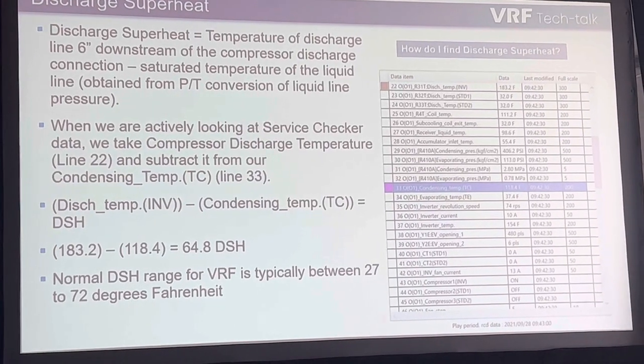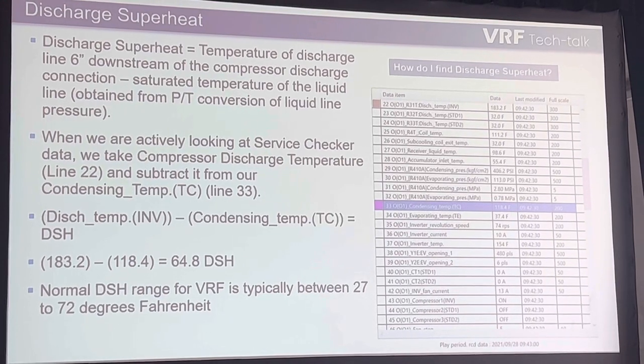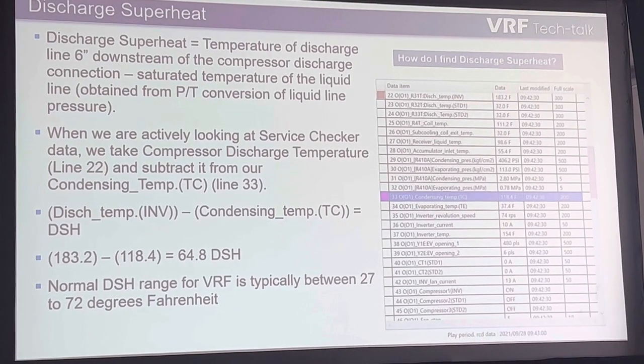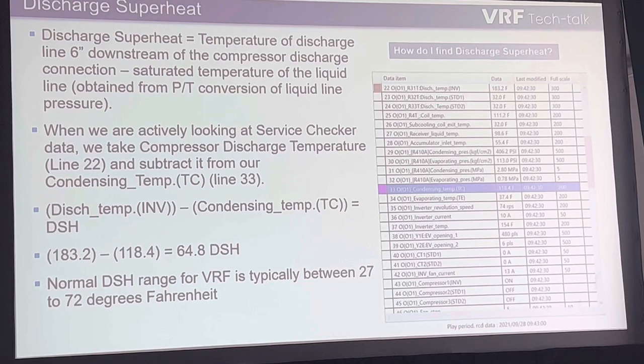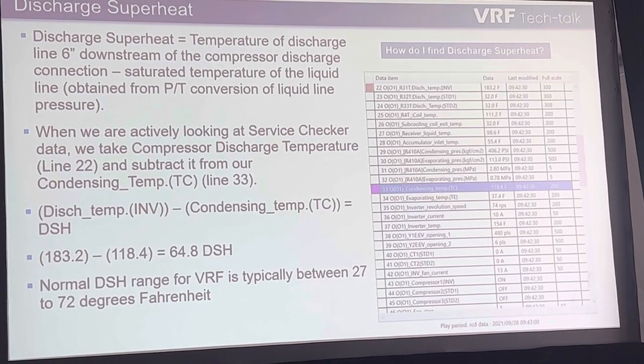A 64-degree discharge superheat reading. Most VRF manufacturers are looking for anywhere from a 27 to 72 degree range for discharge superheat. If we're below that, you're compressing liquid — not 100%, but a version of a mixture. If you're above that, you're not getting enough vapor back, or you don't have enough oil lubricating your compressor.